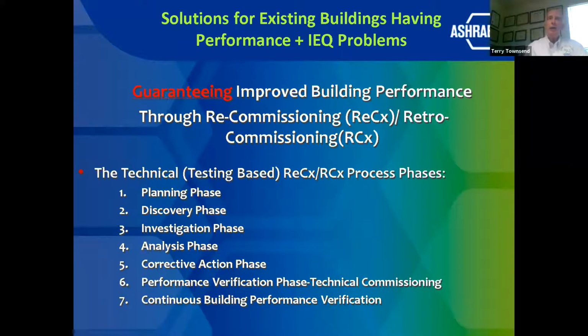Now, how can we guarantee building performance? Well, there are two things that you ought to consider. First is recommissioning, which means that you are commissioning a building that has been commissioned previously, whereas retrocommissioning means that you're commissioning a building that has never been commissioned. And so what I propose is called technical recommissioning, technical retrocommissioning, versus process. Technical is testing based, and there's no sampling, no sampling. Whereas in process, that does allow sampling.